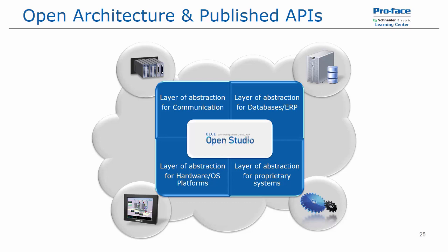With Blue Open Studio, all you would have to do is add the new driver, remove the old one, and then assign your new tags on the driver worksheet with the correct I/O addresses or I/O registers from the device. There is no additional configuration required, and there is no effect on the rest of the application. In fact, you could delete the driver entirely and the application would still operate normally, with the exception of no communication to a device. There are no errors, there are no issues.